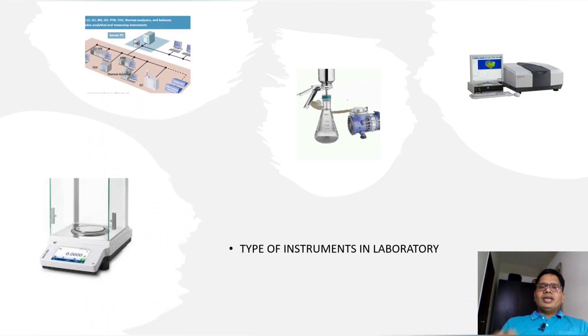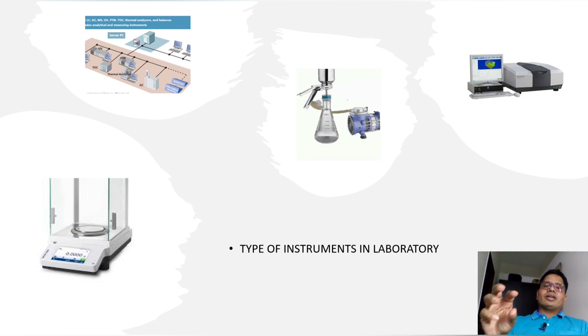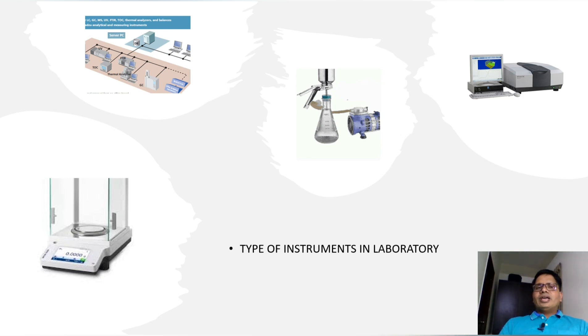The fourth type is a server-based instrument — there are many instruments attached to one server, so all the instrument data goes to the server and is controlled by the server. This is the type of instrument we use in the laboratory. Now let's understand these instrument types as per USP 1058.